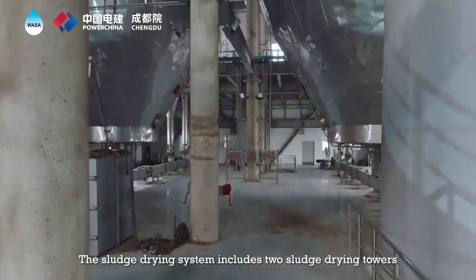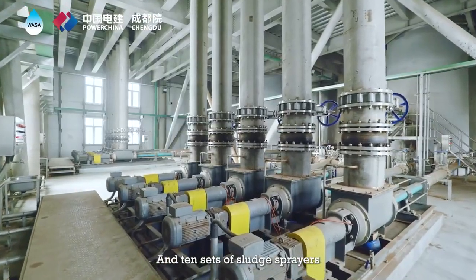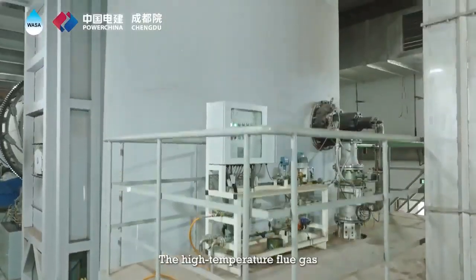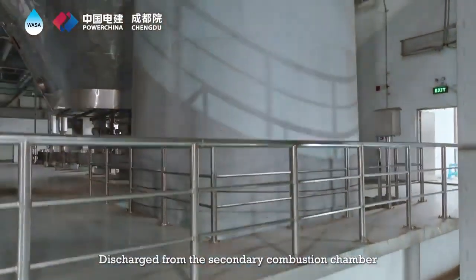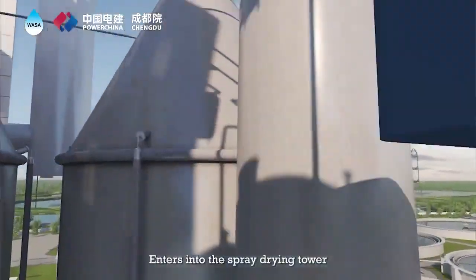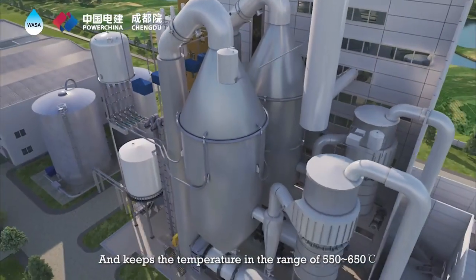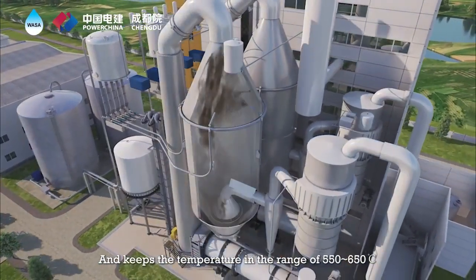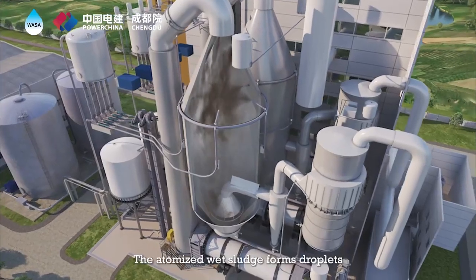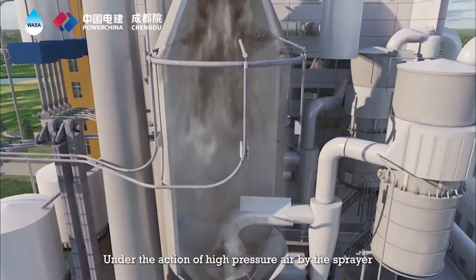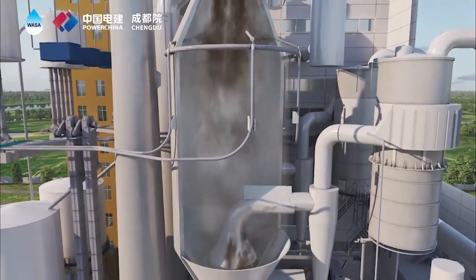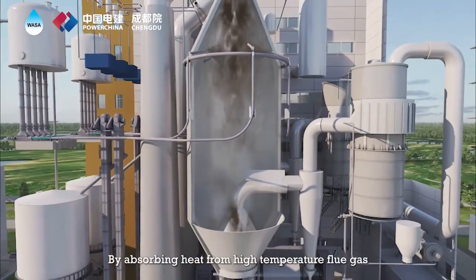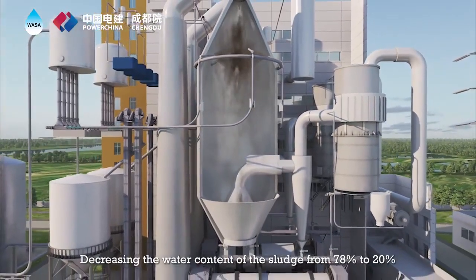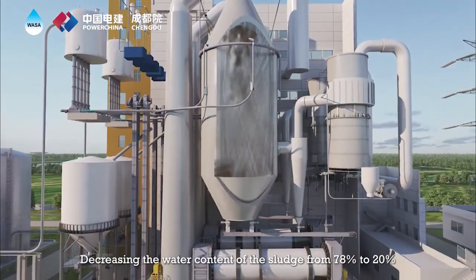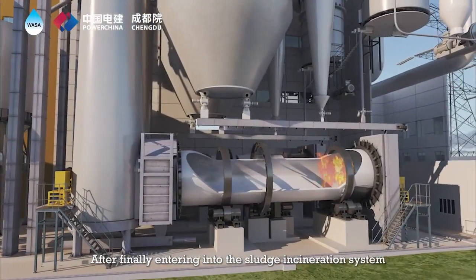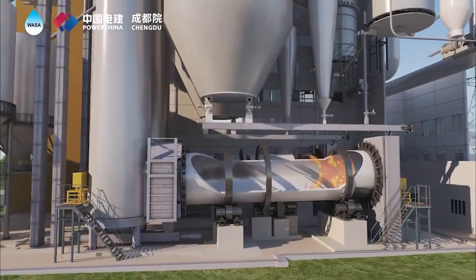The sludge drying system includes 2 sludge drying towers and 10 sets of sludge sprayers. The high-temperature flue gas, discharged from the secondary combustion chamber, enters the spray drying tower and keeps the temperature in the range of 550 to 650 degrees Celsius. The atomized wet sludge forms droplets under the action of high-pressure air from the sprayer, and then the wet sludge dries by absorbing heat from the high-temperature flue gas, decreasing the water content of the sludge from 78% to 20% before finally entering the sludge incineration system.